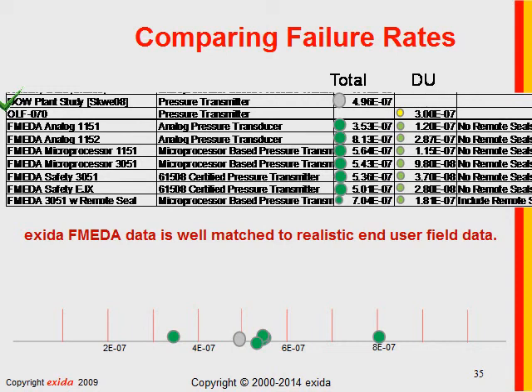Dow includes all types of pressure transmitters — old designs, new designs, microcomputer-based, old analog transmitters, and some safety transmitters. It appears that an average of all these different types comes in pretty close to the Dow number. Taking data from OLF 070 from the PDS database — 3e-7 — dividing by half to account for site-specific versus product-specific data and dropping that on the chart, the FMEDA results are a pretty close match.